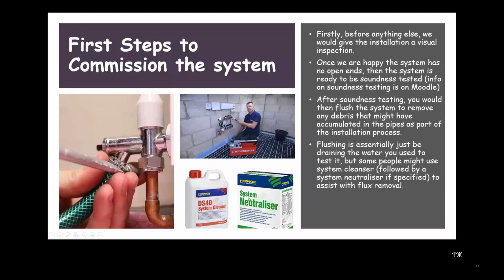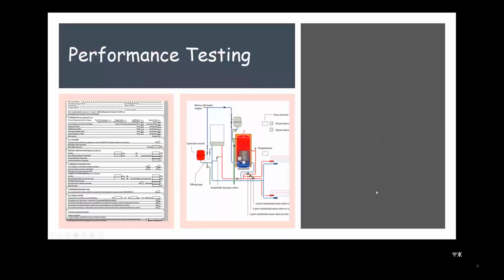Some people might carry out the flushing with a system cleanser, followed by a system neutralizer in some cases if it's an acidic cleanser. And that can help remove more flux. But it's not necessary. You could potentially just flush it with wholesome water, but sometimes with heating systems, people might add system cleansers followed by system neutralizer if required to assist with flux removal. So when the system's been flushed, you then refill with water and carry out the performance test.